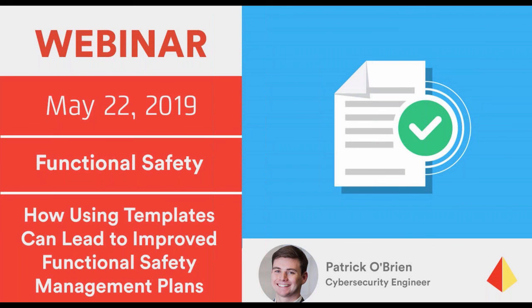And then for an expert, this might be what's required more for, say, a functional safety assessment. So having that independent expert level to come in and do your cold eye review. For demonstrating that expert requirement, you might require that a specific personnel certification be in place. You might require, instead of a couple years of experience, 5 to 10 years of experience. And so that's your specific personnel requirements for that expert level. By documenting those different tier levels, you're able to fit it to the specific needs of that individual task, and that seems to give a good amount of flexibility.